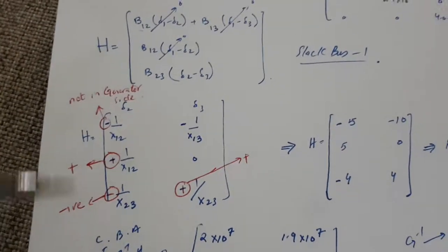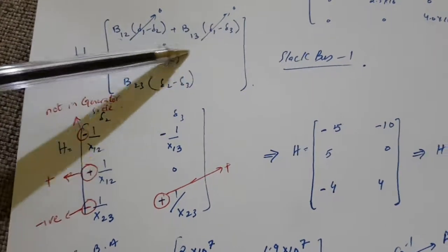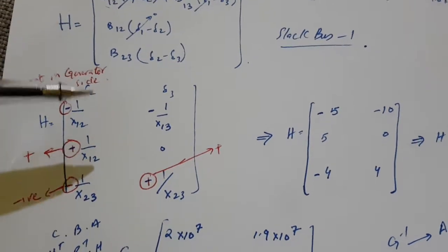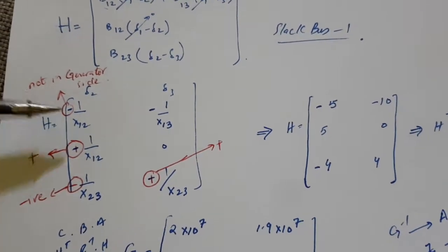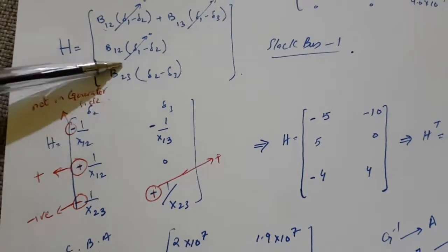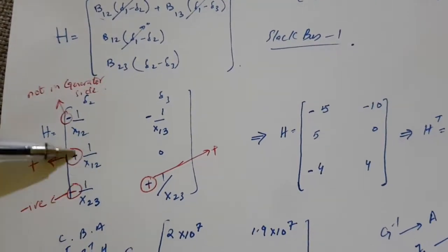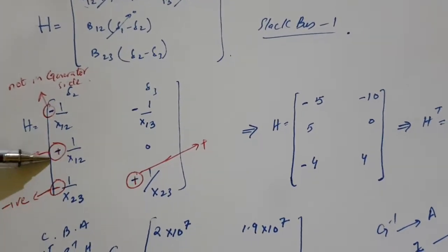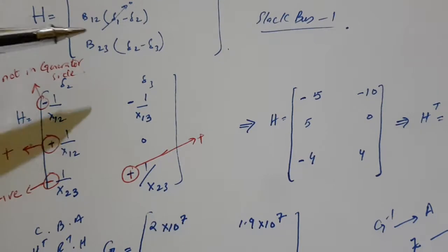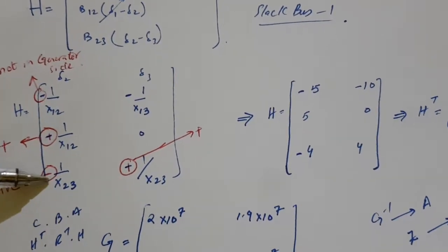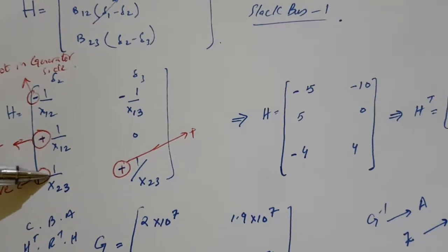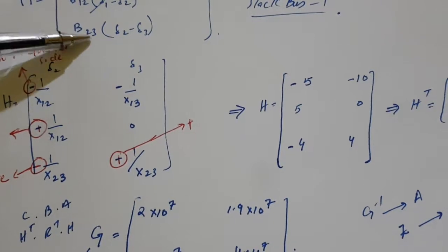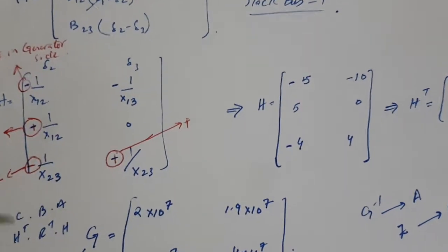Be careful: when talking about the generator, do not apply this sign inversion. For the generator, keep the same signs. So for line 1-2, it must be (-1/x12) but since the flow is from 2 to 1, I have taken it positive. Similarly, this must be positive but I have taken it negative because the flow is from 3 to 2. That is why I have changed these signs.